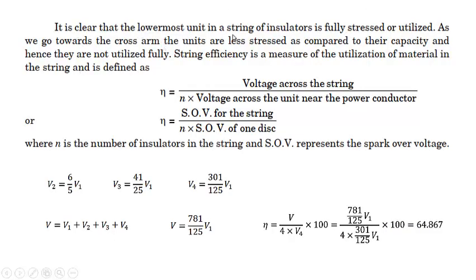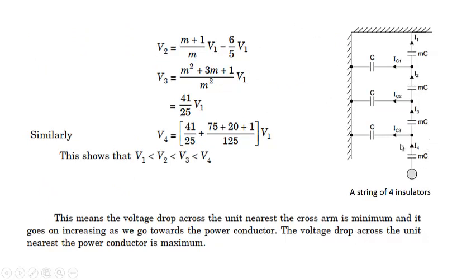So it is clear that the lowermost unit in a string of insulators is fully stressed or utilized. As we go towards the cross arm, the units are less stressed as compared to their capacity, and hence they are not utilized fully. So that means we have to design the insulators in such a way that the maximum voltage occurs across this, and its rating should be equal to the maximum voltage appearing. But when we do that and use the same identical insulator disks, the voltage across this will be less, the voltage across this will be still lesser. That means this one is utilized fully, but other insulators are not utilized fully for the same voltage level.